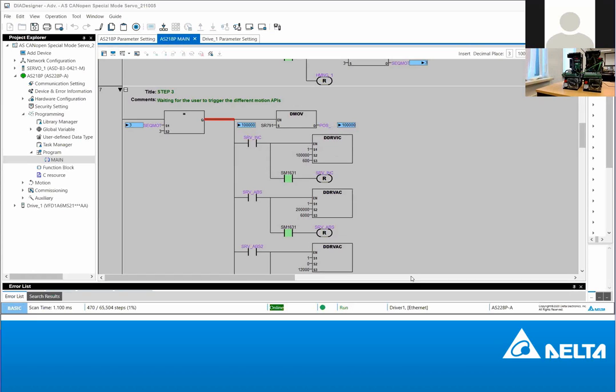So we got an answer from one of our colleagues. It will increment 100,000. Perfect. That is the absolute answer. So if I trigger this command again, my drive will displace 100,000 more. Then the current position is going to be 200,000. So just watch this. What will happen here? Watch the shaft. It's going to move. Thank you for the answer. A trigger. You see the drive is moving. Now it has stopped. Position 200,000.